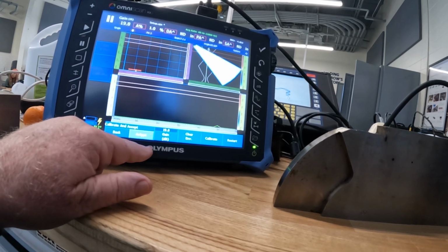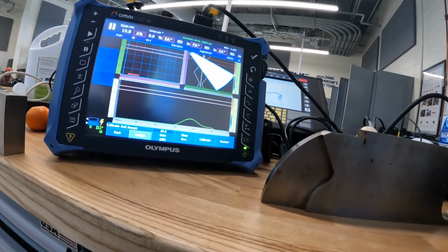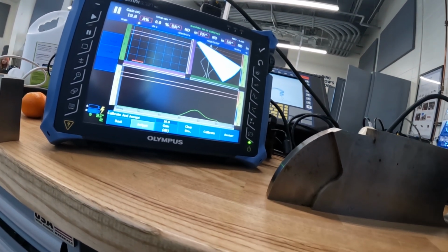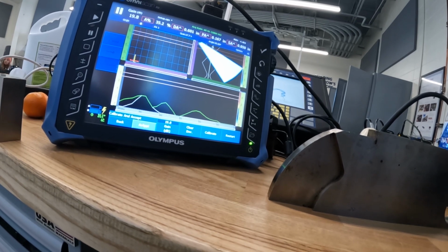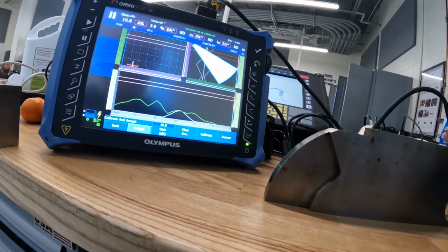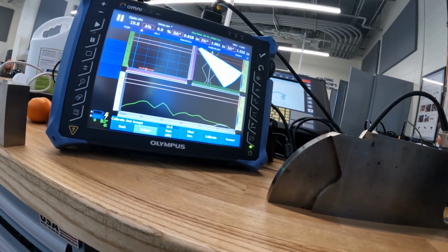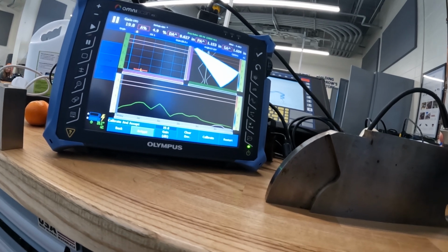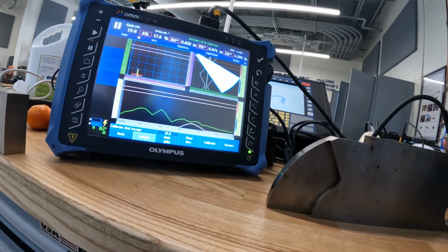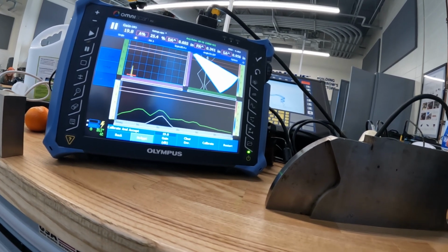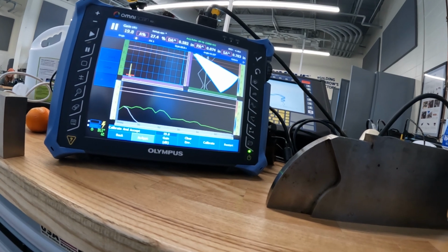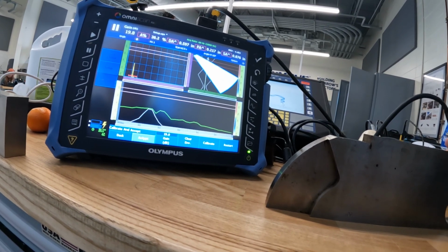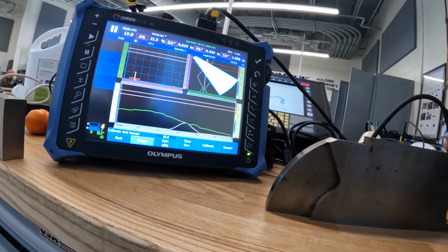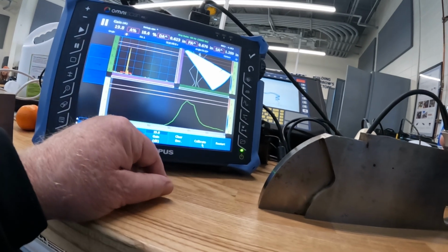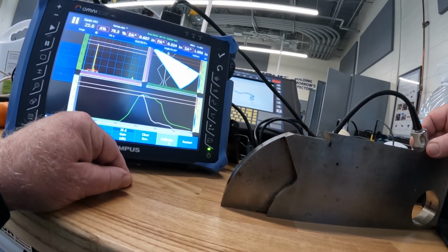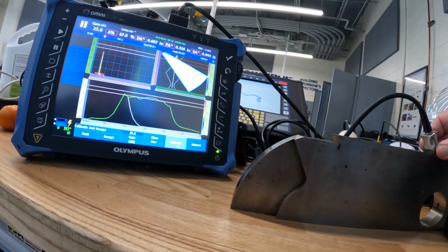Here we go again. So I have to get my signal. Start off over here. And back. Make sure I've got plenty of pressure on the front part of my wedge. Make sure I'm getting good response. If you don't get it peaked out properly as you go across, I always say you can see your bone. If you can't see your bones when you're pushing on the transducer, you're not pushing hard enough. Hit calibrate. And so the end result is I want to be able to get within the error bars with my sensitivity after I've done my calibrate, like this.